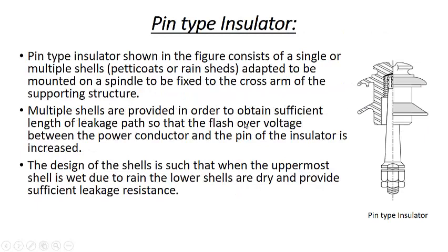So it means that the length from this center to this center should be less than the length from this point to this point. It is because when the flashover occurs, it should occur between this conductor and this pin, so that it results in damage to the insulator. If this is more distant than this, there may be a possibility that flashover may occur between this and the cross arm, which is placed like this, and the cross arm may be damaged. And we know that the cross arm is costlier than this insulator, so in that case we have to replace the cross arm.